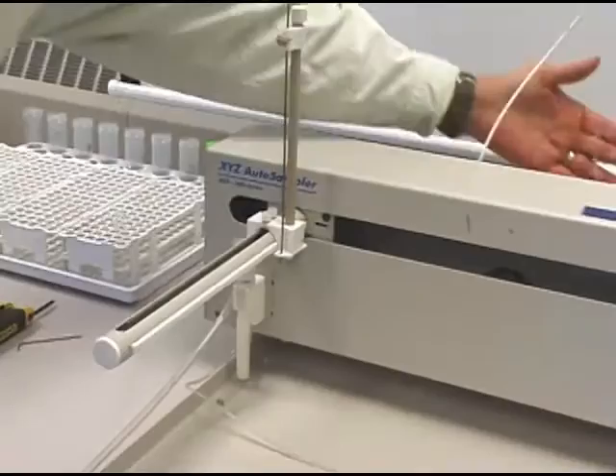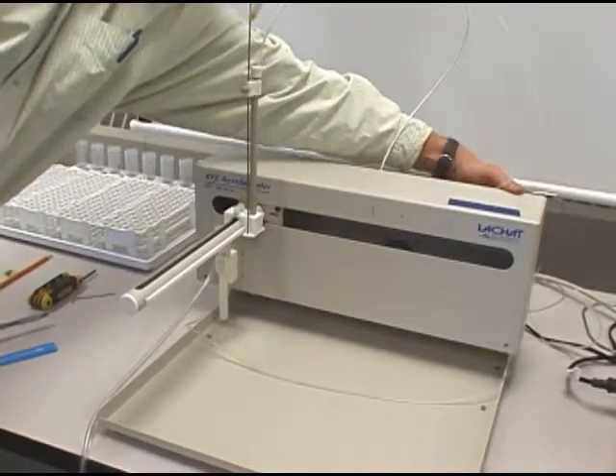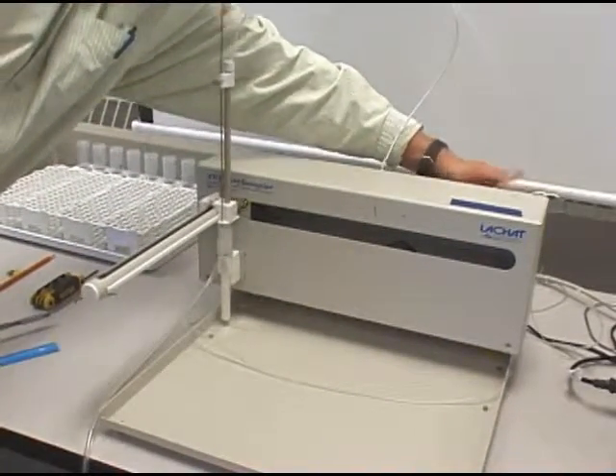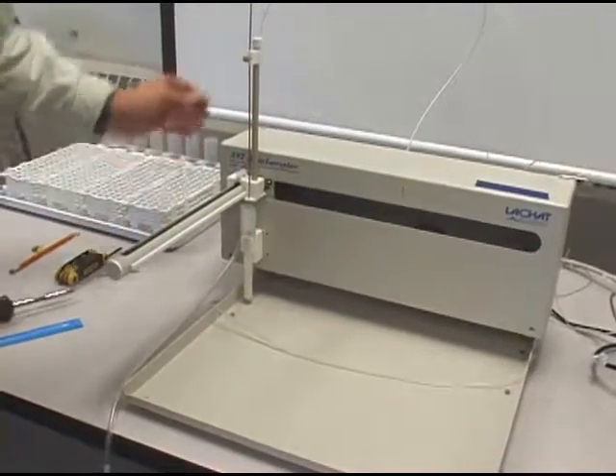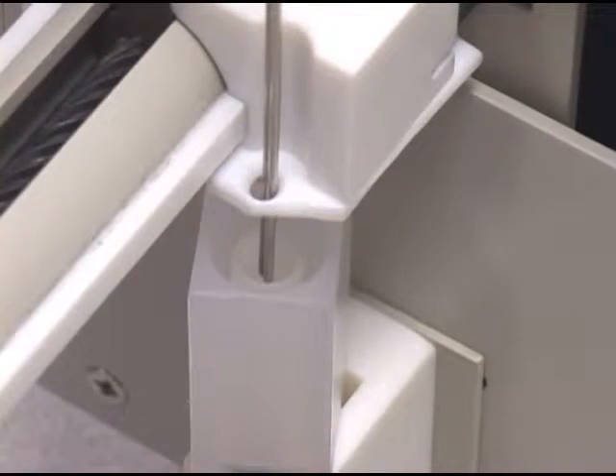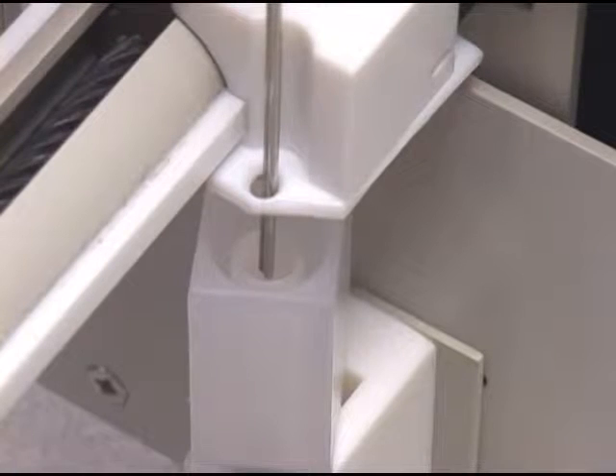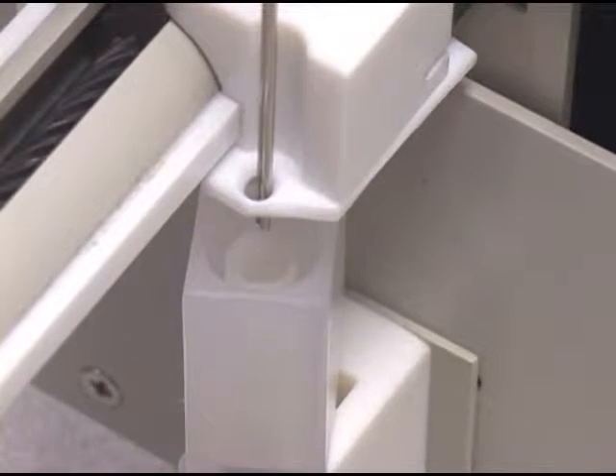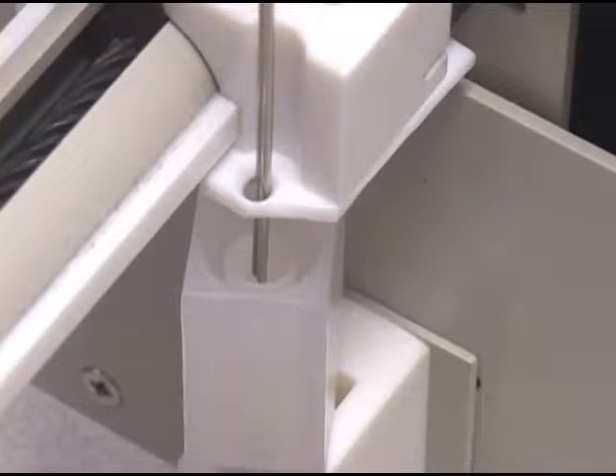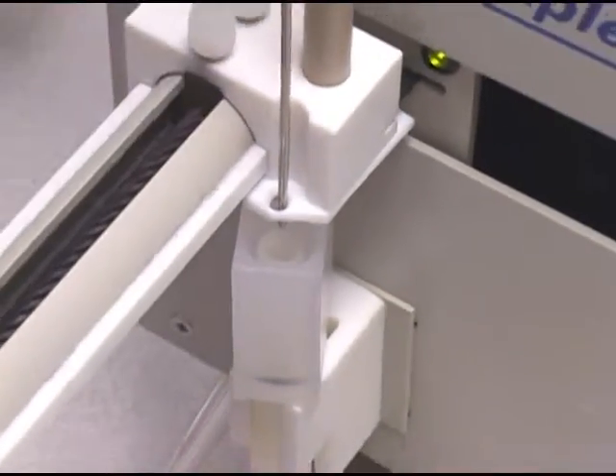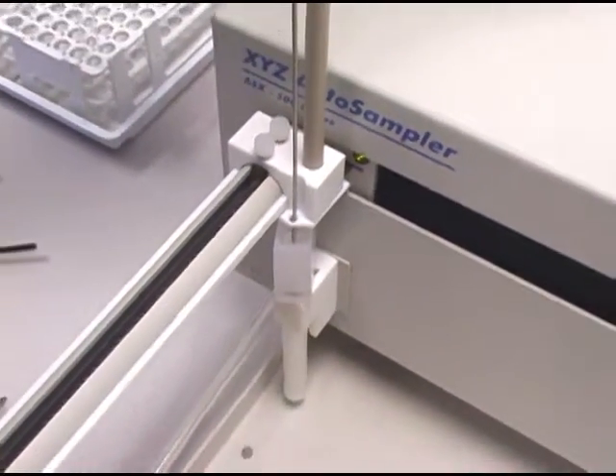And now I'll turn the instrument on and off to let it center itself, or turn it back on, and check the position of the probe. You can see now that the probe is pretty much centered on the X-axis, but it is still a little bit forward, so we need to adjust it back a little bit.